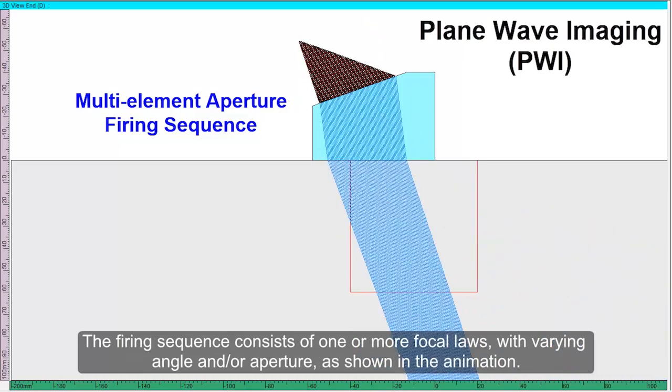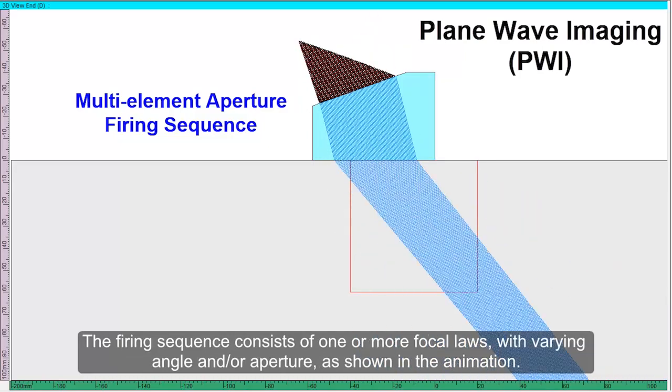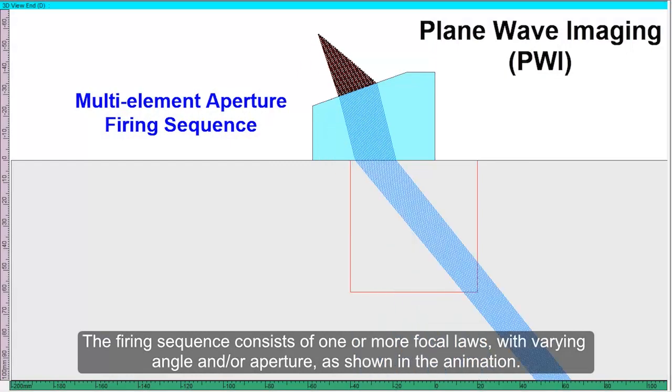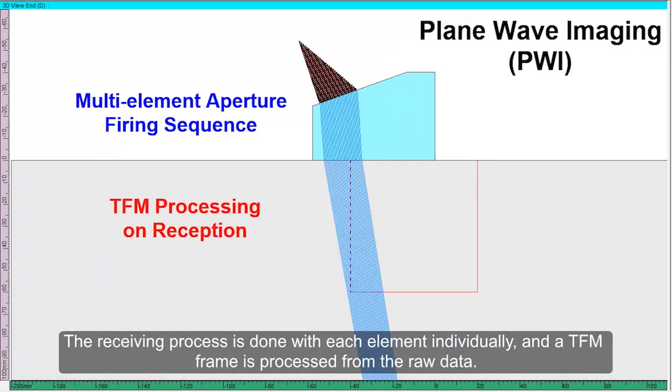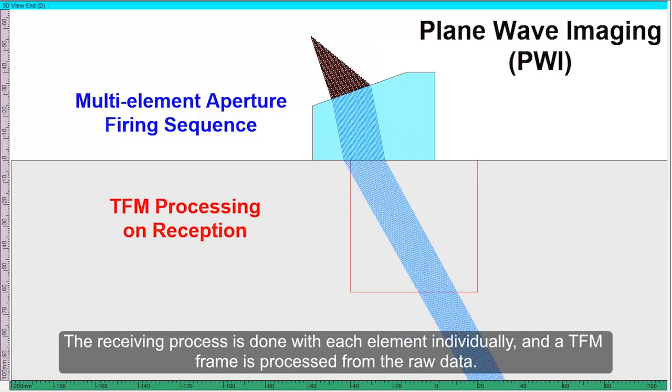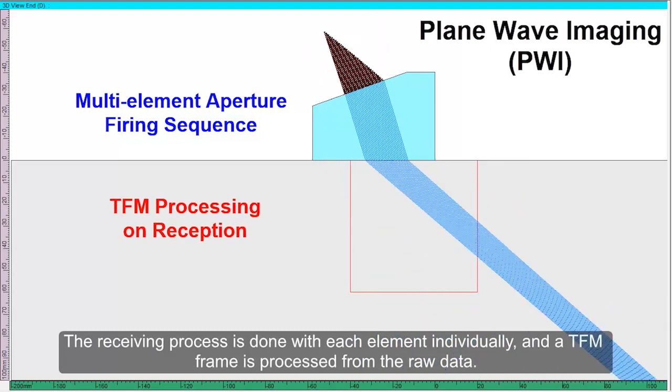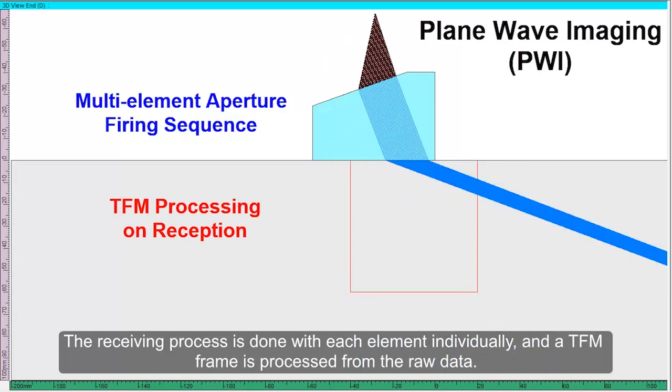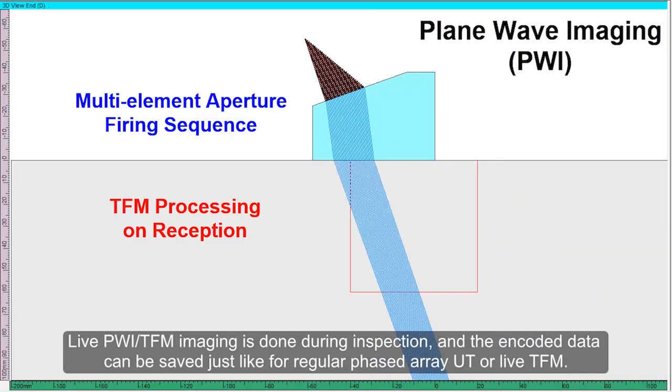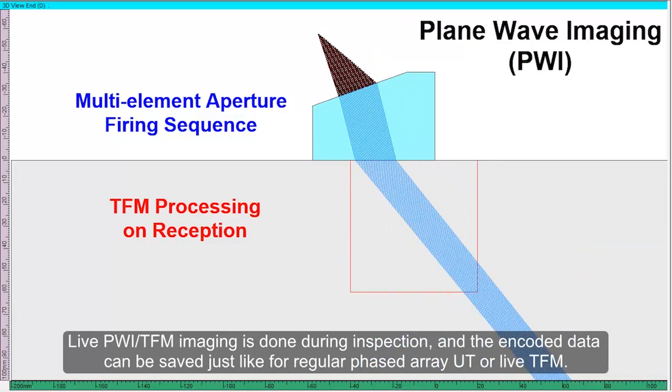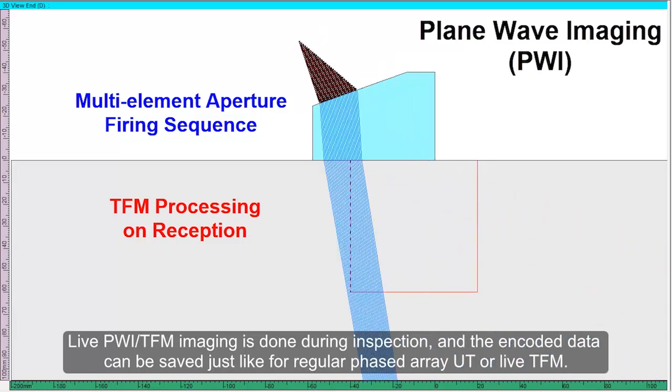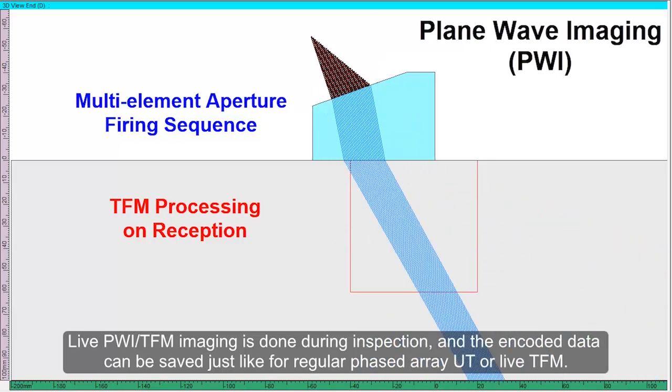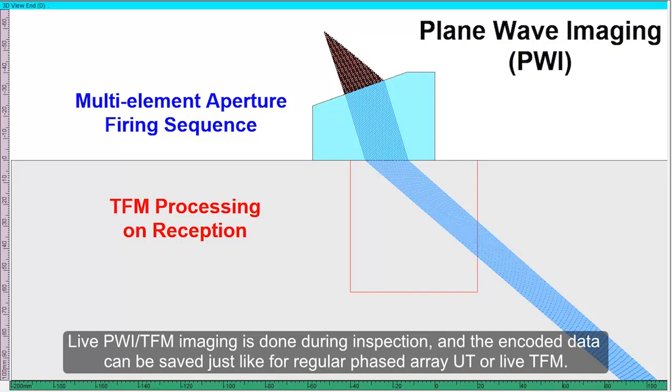The firing sequence consists of one or more focal laws with varying angle and/or aperture as shown in the animation. The receiving process is done with each element individually and a TFM frame is processed from the raw data. Live PWI TFM imaging is done during inspection and the encoded data can be saved just like for regular phased array UT or live TFM.